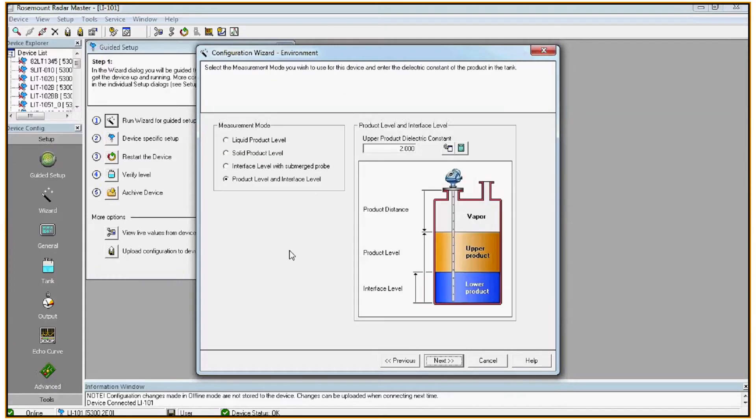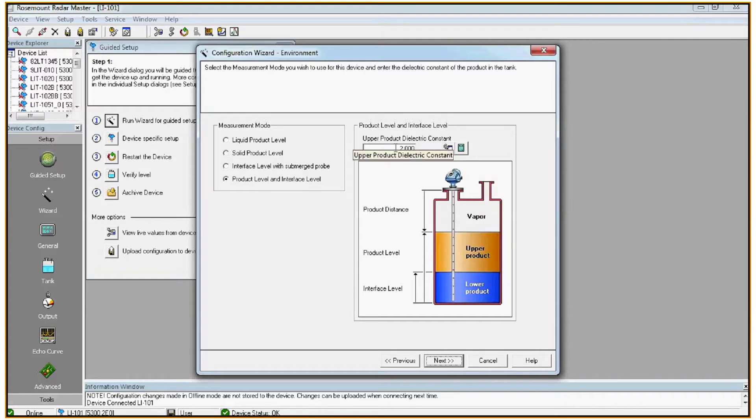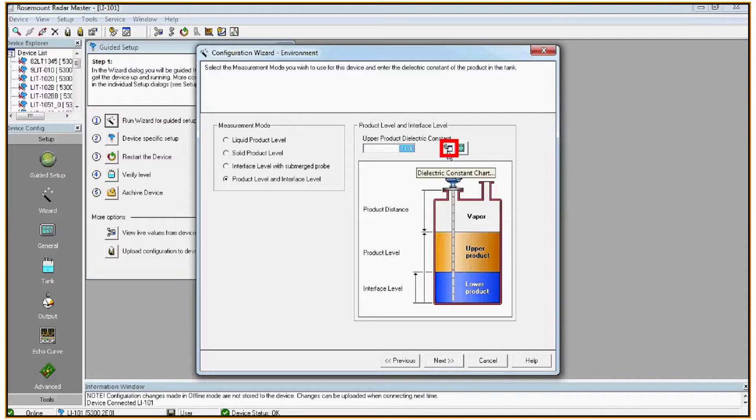Here we configure the measurement mode. For this example I will use product level and interface level. When doing an interface application, it's very important that you program in the upper product dielectric constant. For most refined oils it will be about two. If you're unsure for your product, just click on this button, the dielectric constant chart, and it'll give you a list of different products to choose from.